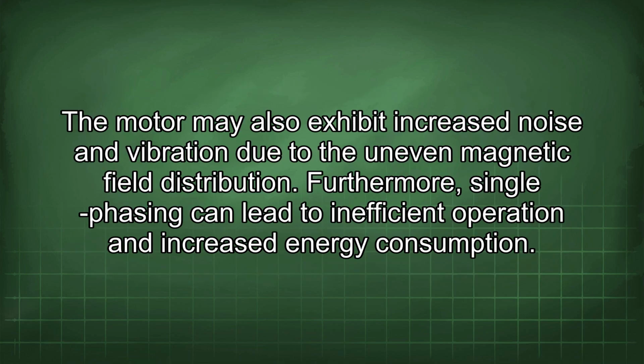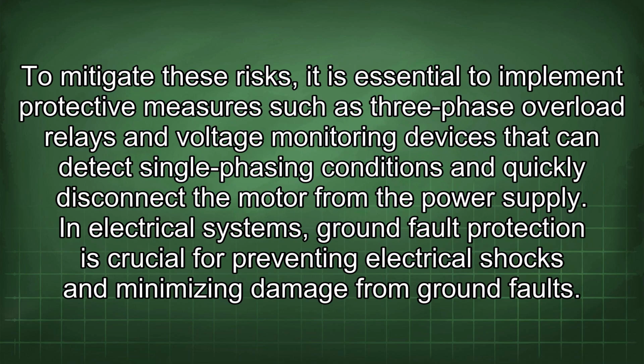The motor may also exhibit increased noise and vibration due to the uneven magnetic field distribution. Furthermore, single-phasing can lead to inefficient operation and increase energy consumption. To mitigate these risks, it is essential to implement protective measures such as three-phase overload relays and voltage monitoring devices that can detect single-phasing conditions and quickly disconnect the motor from the power supply.